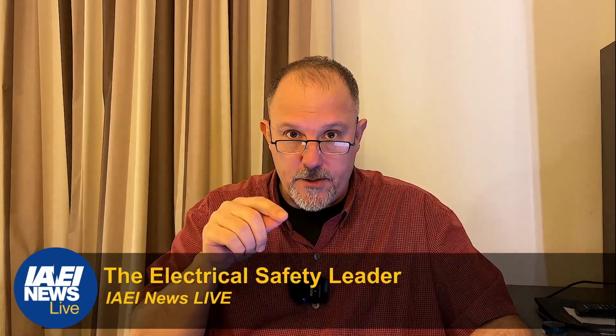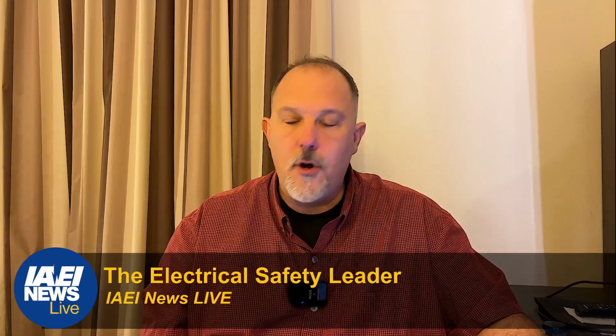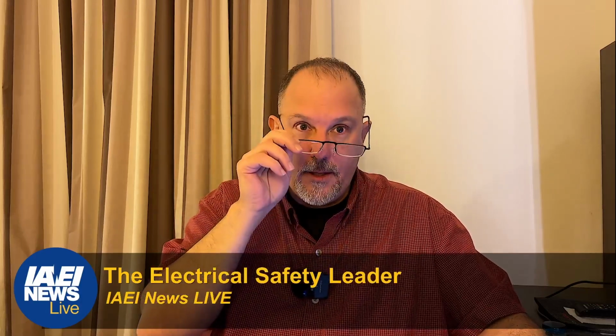Understanding the parts of a receptacle. That's another important thing to wrap your head around. Take a look at that receptacle. Understand what the yoke is and how that's assembled, because we use that yoke for a couple of different things. Obviously, we use it to hold the receptacles together, but we also use the yoke to hold the receptacle in the outlet. Now, while not prevalent, there are non-metallic yokes. You may or may not have seen them because you don't see them every day, but the yoke doesn't have to just be metal.